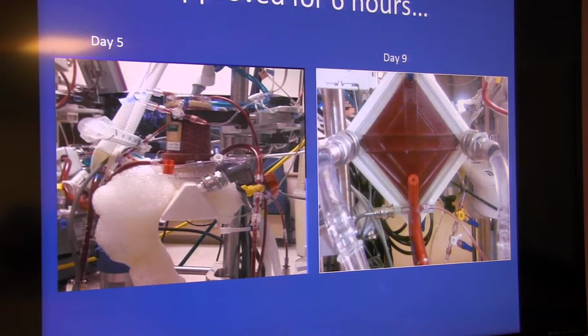So if your oxygenator is failing from the standpoint of acting as your lung, what you're going to hear is that when you come in the morning, you're going to realize that your sweep speed instead of being 0.4 is now today up at 0.8, or your FiO2, which was 50 yesterday, is now 75, but your pre and post gases will probably be fairly similar. Does that make sense? So some places just set the FiO2, for example, and don't worry about titrating it, so then when you hear the post-oxygenation PaO2, you know where it's varying. For us, we titrate our FiO2 to keep the PaO2 greater than 250, so you do have to be aware of what your FiO2 was the day before, which to me is, again, just like a ventilator. When you hear a blood gas in your patient, you think about what your ventilator settings are. Here, you don't have to worry about tidal volume and rate, and FiO2; all you have to worry about is sweep speed and FiO2. Make sense?